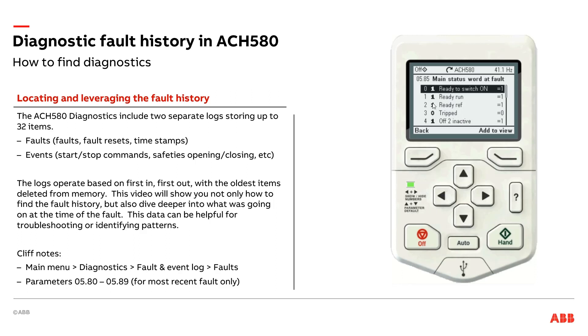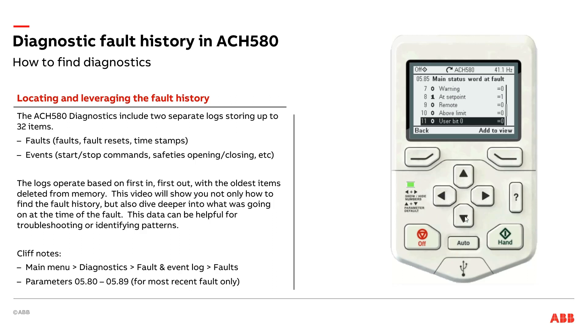It tells me one means yes, this was made; zero means no, it wasn't made. So I wasn't tripped beforehand — I was ready to run. You can scroll through and see all the different things it'll tell me exactly when it faulted. One of the ones I like to look at is whether there was any active warning at the time of fault — was this something that came up slowly? The drive might give a warning before it faults. In this case I just popped the control panel right off, so there was no warning. But maybe it was a temperature related issue — the drive might have been throwing an over-temperature warning for a while before it eventually had to fault out, maybe because the cooling fan had gone bad or the drive had gotten too dirty to cool itself. You've got a lot of details here as part of your troubleshooting.